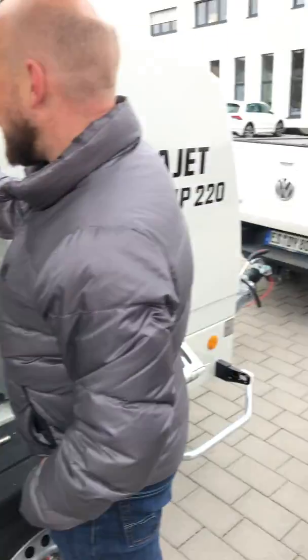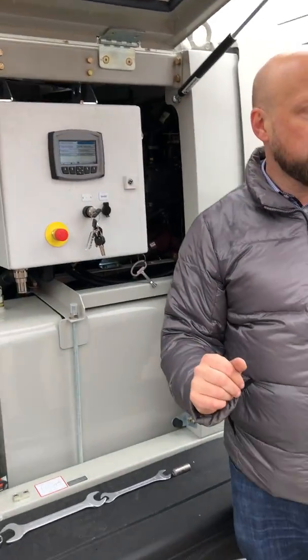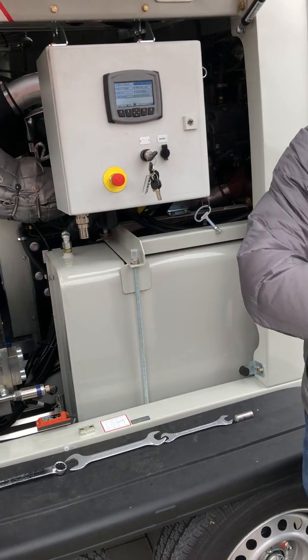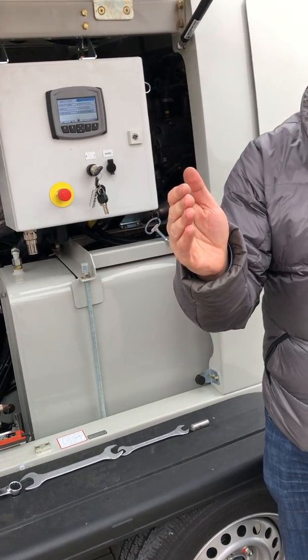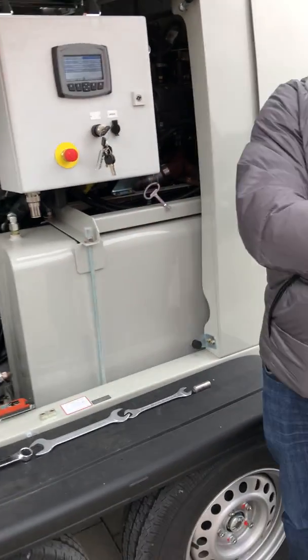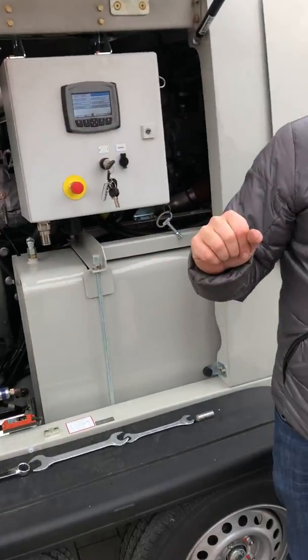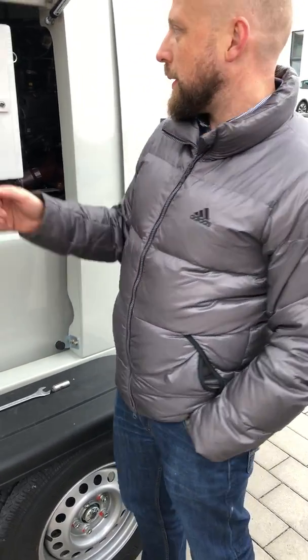And then you have the date as well? No, just because you would have 18 dates. We only know that it happened this often. If it's only like 5 pages, if you rent out the machine, I would recommend to just take your cell phone and make screenshots, and you see what happened. But you also have the fault history of the last 30 errors, when they happened and what happened, and what pressure. So you have both.